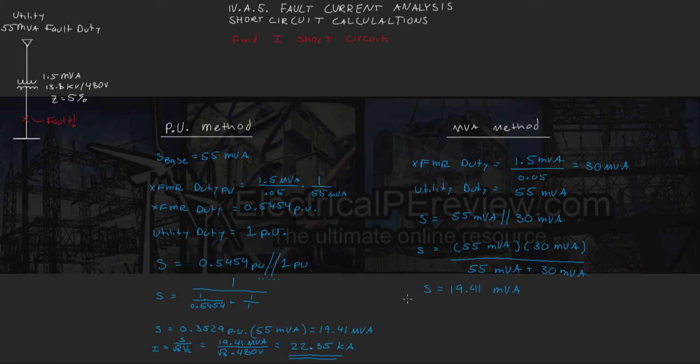And then to find the actual current flowing through the fault in this direction right here, we do the same like we did when we were using per unit. Since S equals VI, we can solve for I by dividing by V. So I is going to equal 19.41 MVA divided by square root 3 times our line voltage of 480V. And of course we get the same answer of 22,350 amps or 22.35 kA.